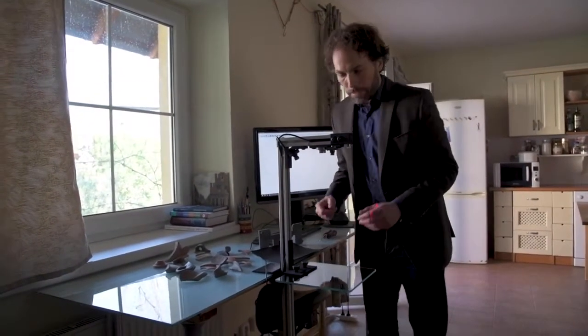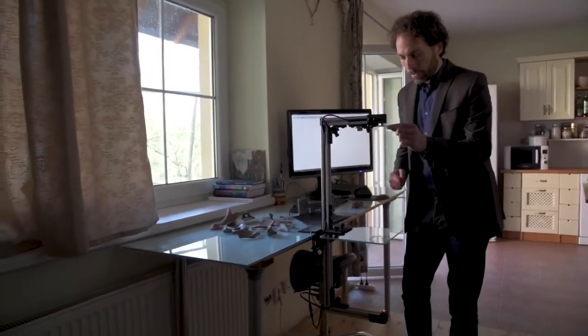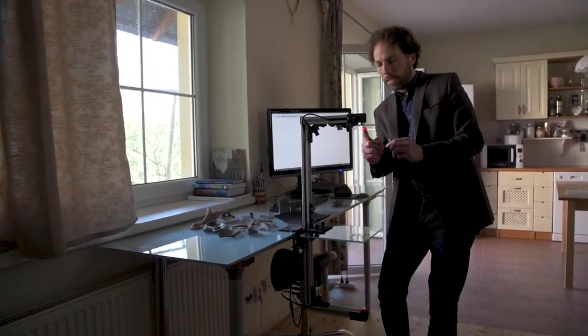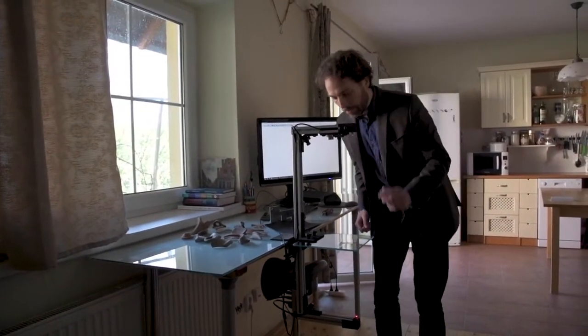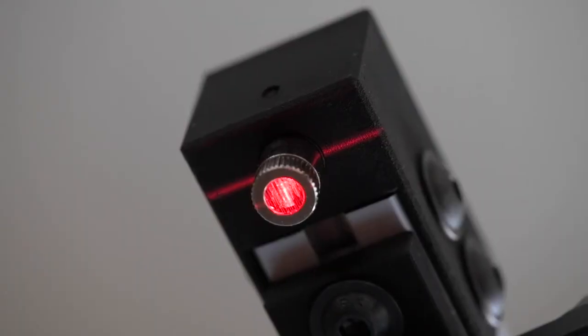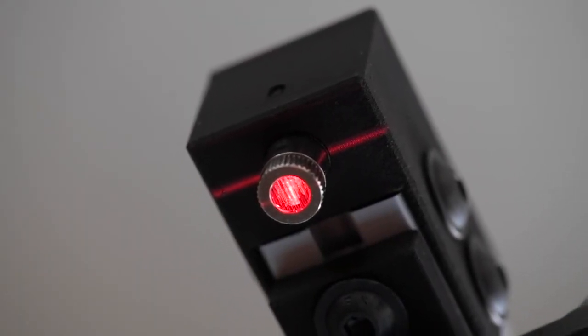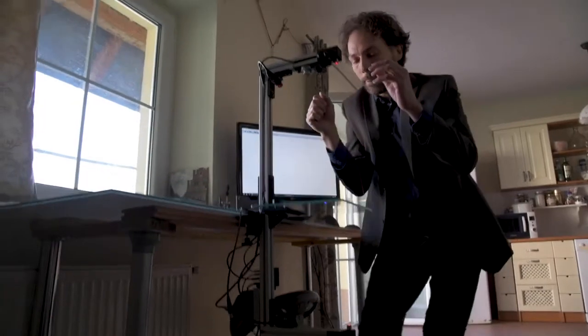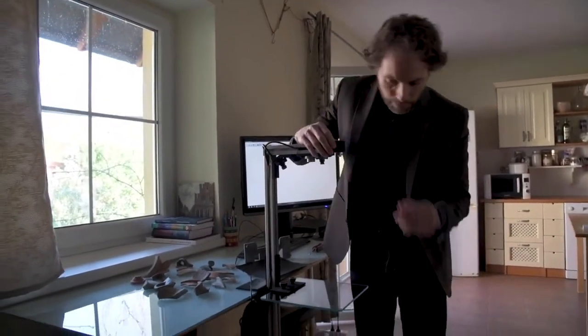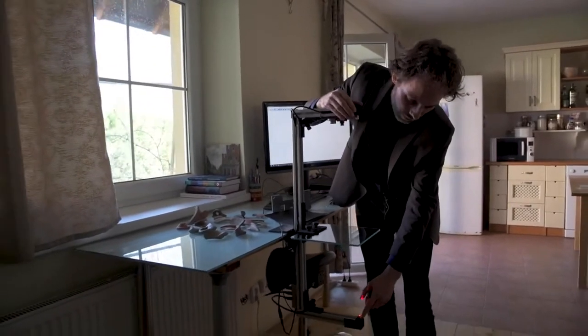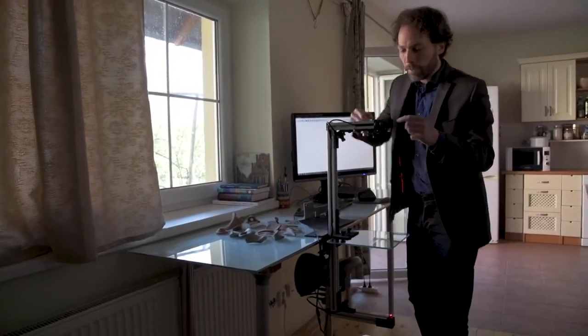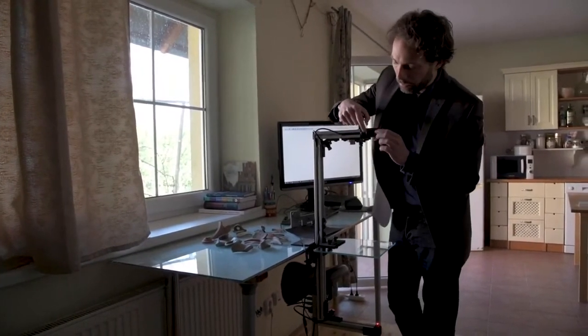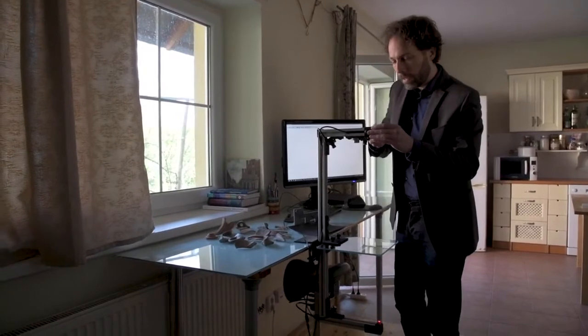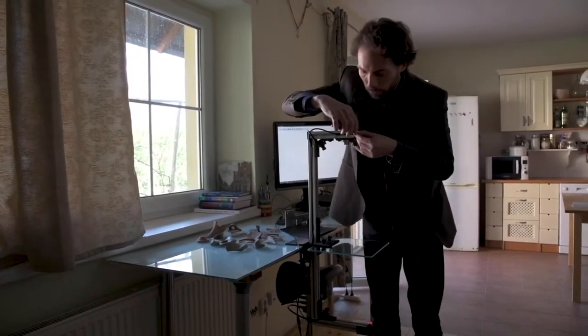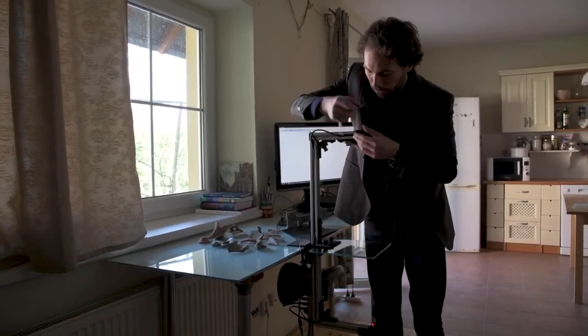The first thing is I have to make sure that each of the laser lines is projected exactly in the middle of the opposite projector. So I check the upper laser projector, illuminated by the lower one, and we see the line going exactly through the middle, through the center, so that's okay. But looking at the lower one, we see that the line from the upper one is mismatched. There are four screws on each side of the mounting of the laser projector. I have to loosen them a little. Not too much, just so that I can move it.